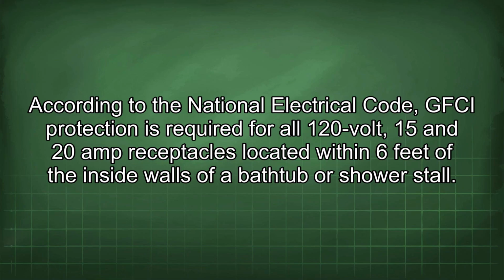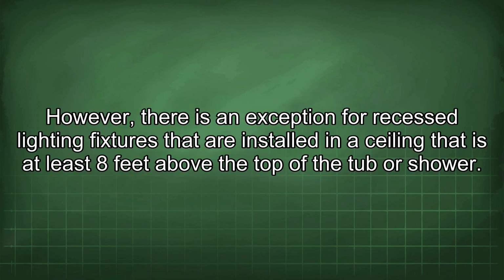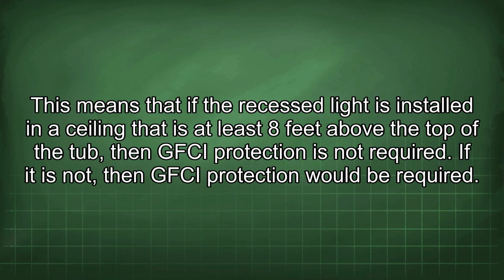According to the National Electrical Code, GFCI protection is required for all 120-volt, 15 and 20 amp receptacles located within 6 feet of the inside walls of a bathtub or shower stall. However, there is an exception for recessed lighting fixtures that are installed in a ceiling that is at least 8 feet above the top of the tub or shower. This means that if the recessed light is installed in a ceiling that is at least 8 feet above the top of the tub, then GFCI protection is not required. If it is not, then GFCI protection would be required.